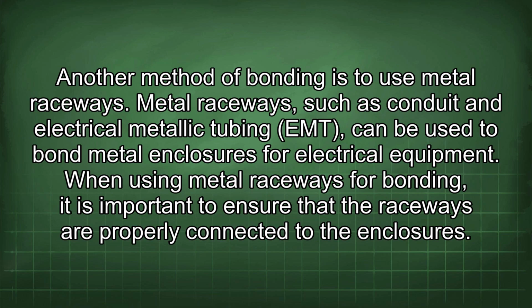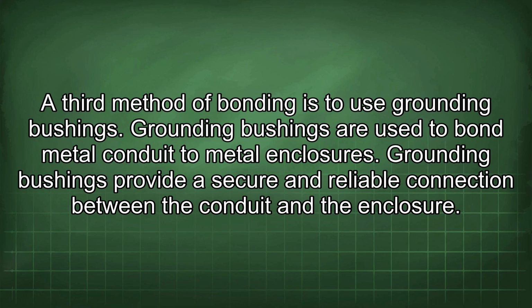Another method of bonding is to use metal raceways. Metal raceways, such as conduit and electrical metallic tubing (EMT), can be used to bond metal enclosures for electrical equipment. When using metal raceways for bonding, it is important to ensure that the raceways are properly connected to the enclosures. A third method of bonding is to use grounding bushings. Grounding bushings are used to bond metal conduit to metal enclosures. Grounding bushings provide a secure and reliable connection between the conduit and the enclosure.